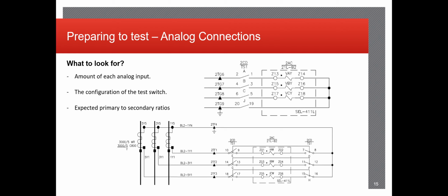So when you're plugging in your voltages and currents, you always need to go look at the prints to, number one, point-to-point check that everything is lined up correctly into the relay and possibly test switches if available, and also understand what phase should go where when you're plugging in your relay test set. You also see, especially with the currents here as an example, the ratios that apply. This is something that you'll also be measuring as well.